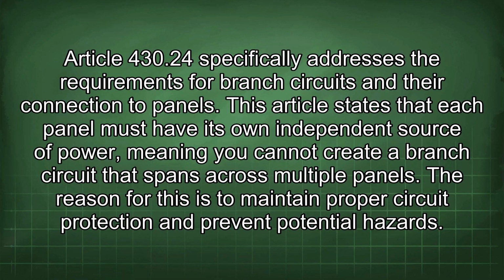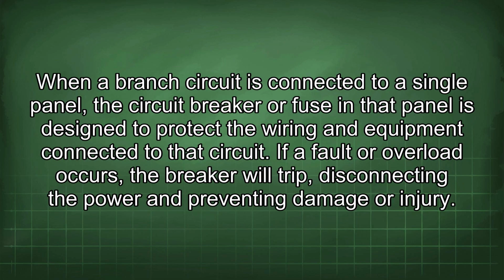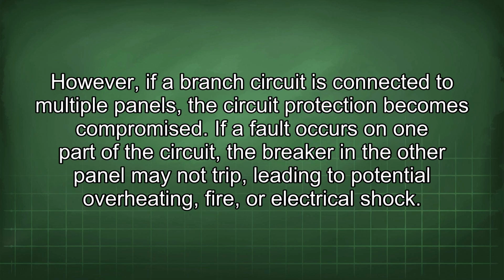The reason for this is to maintain proper circuit protection and prevent potential hazards. When a branch circuit is connected to a single panel, the circuit breaker or fuse in that panel is designed to protect the wiring and equipment connected to that circuit. If a fault or overload occurs, the breaker will trip, disconnecting the power and preventing damage or injury. However, if a branch circuit is connected to multiple panels, the circuit protection becomes compromised. If a fault occurs on one part of the circuit, the breaker in the other panel may not trip, leading to potential overheating, fire, or electrical shock.